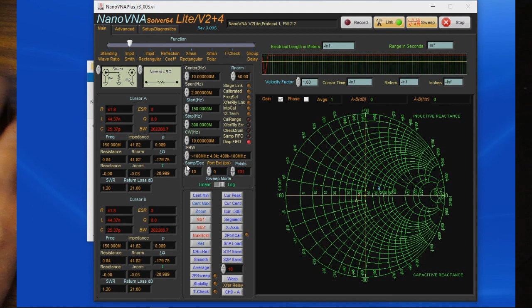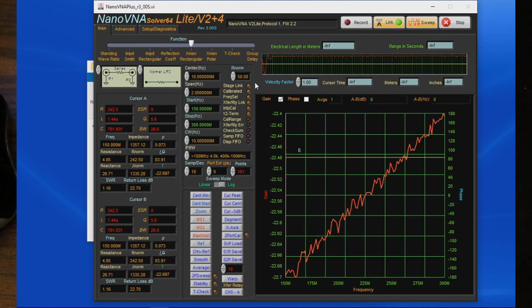And we'll program the start and stop. And let's just change this to 101 data points. I mean, look at the difference in the speed. Let's select the transmission rectangular. I mean, you can see this is quite a bit faster. Let's go ahead and select the diagnostics. So you can see it's updating at about 180 milliseconds. Now again, we can speed this up by changing this E1 register. Let's go ahead and set this to 1. And you can see our sweep time now is about 40 milliseconds or so.